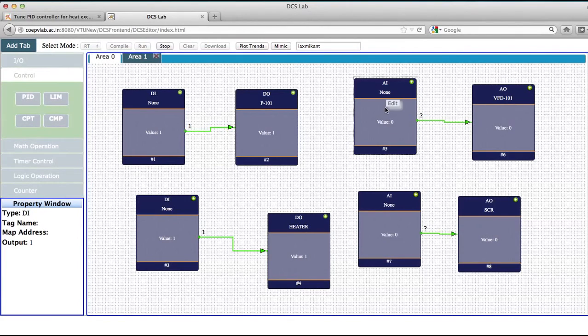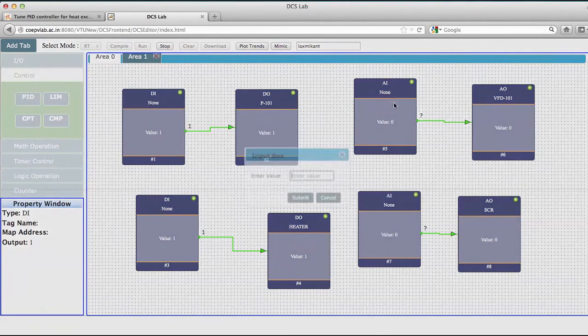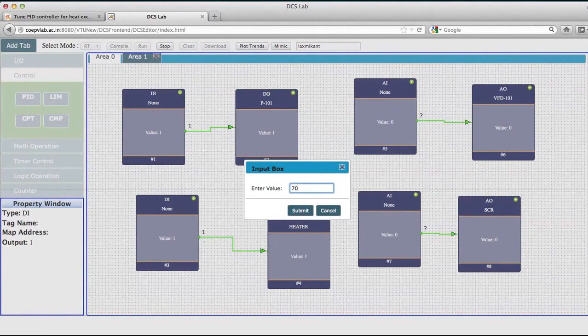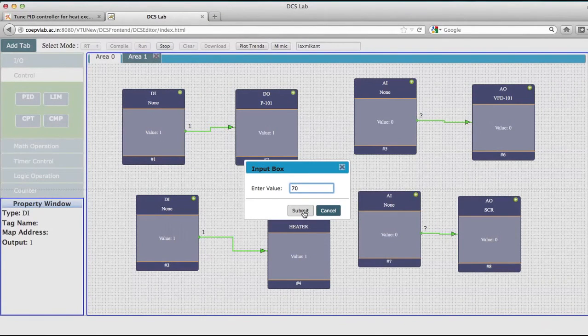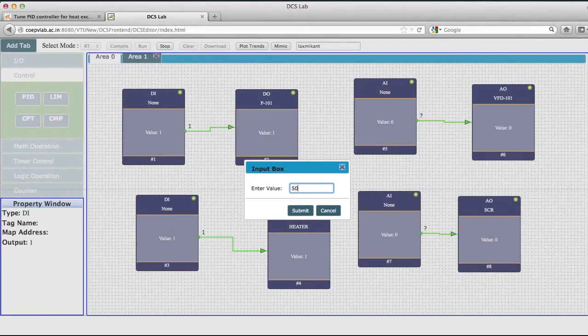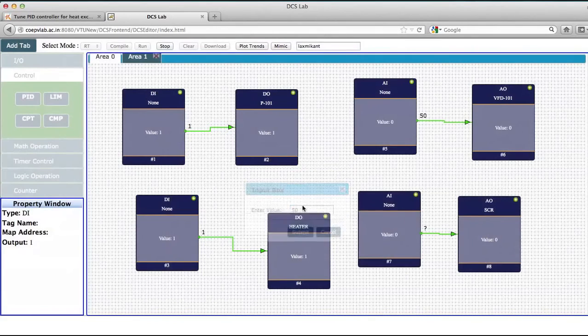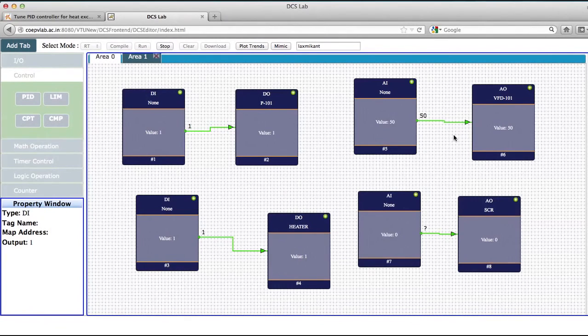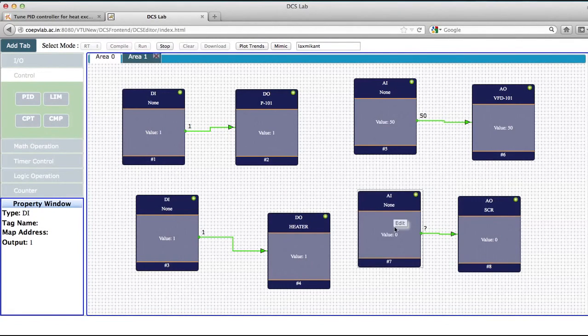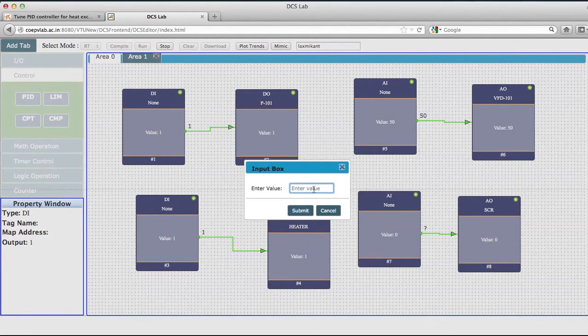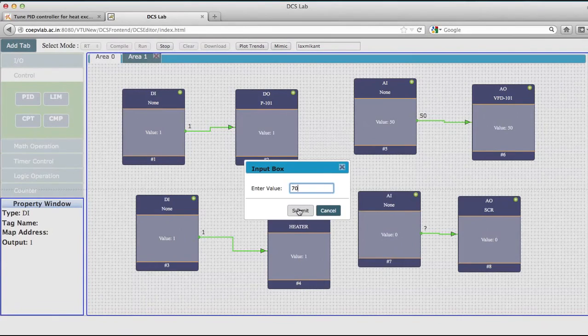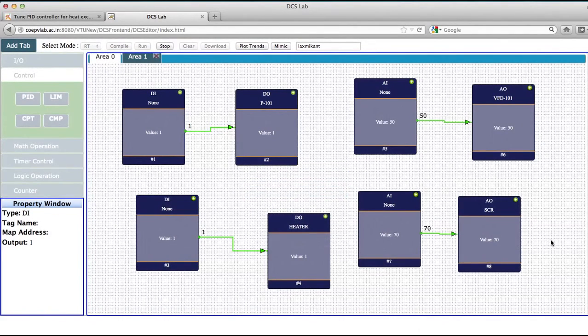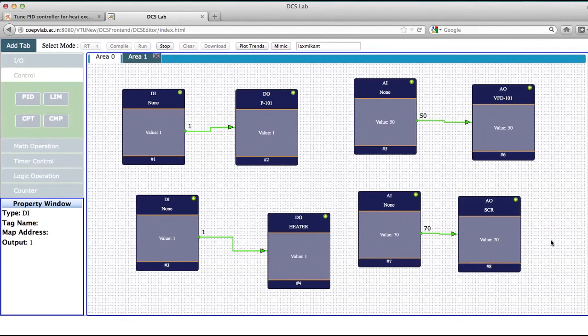And now I have to give value to the SCR. So I will give value to the SCR. For example, if I give this to 70%, and VFD is, I will set it to 50% to start with. So VFD is 50%, that means currently the motor is running at 50% speed. Similarly, the SCR, that is heater SCR, is running at 70%. So I am not giving full heat. So what will happen is the output would become 50 for the pump and 70 for the heater.